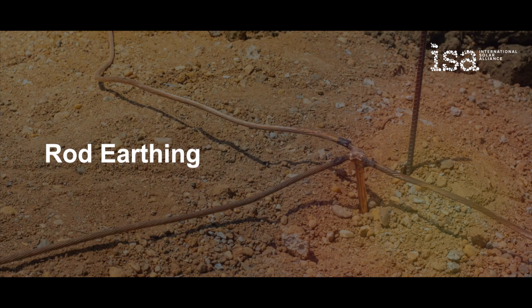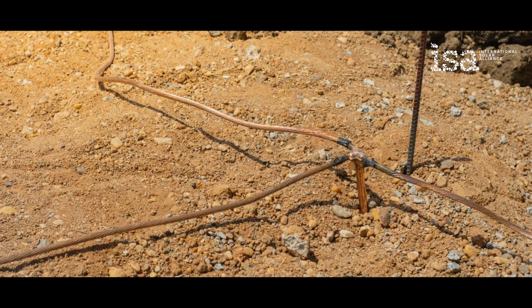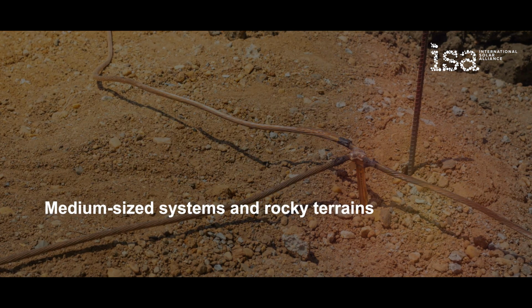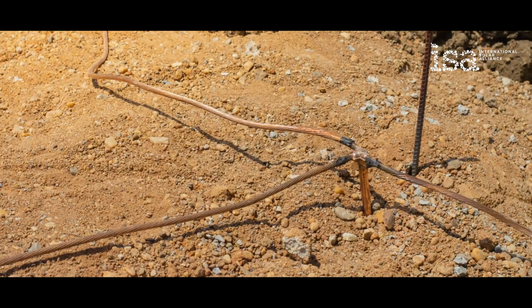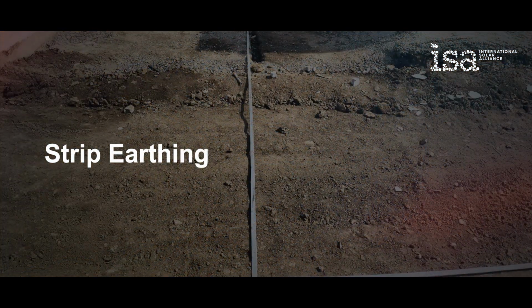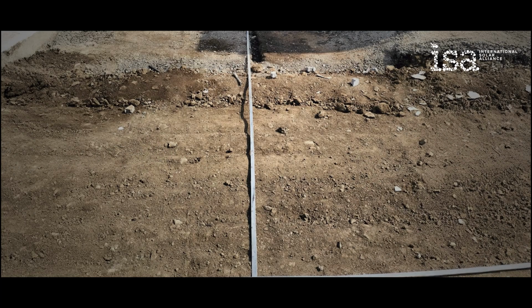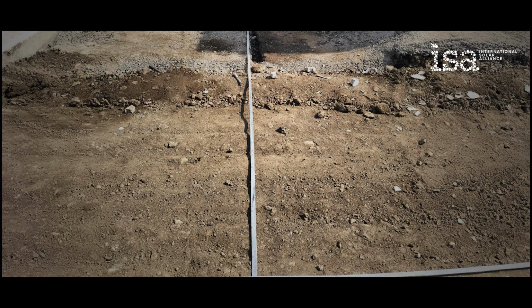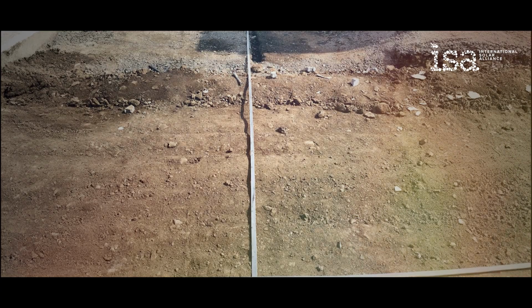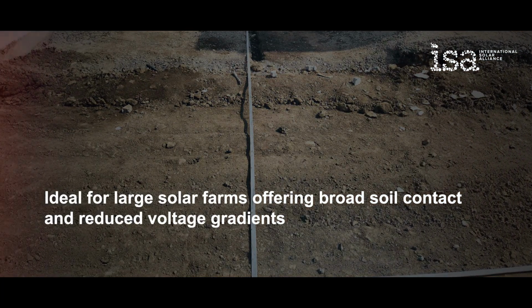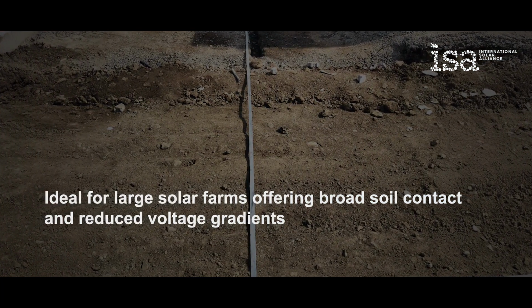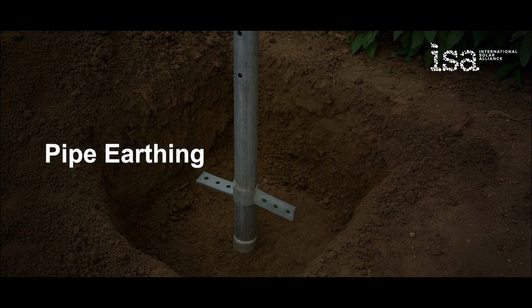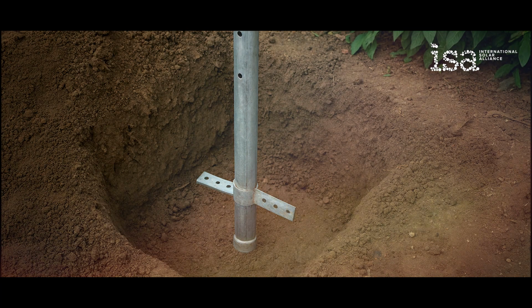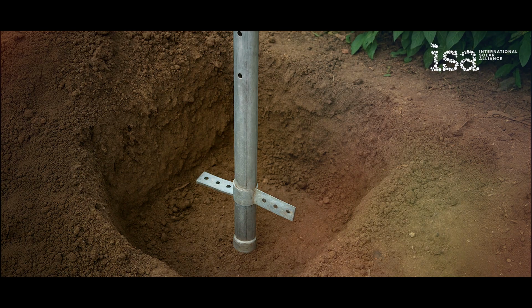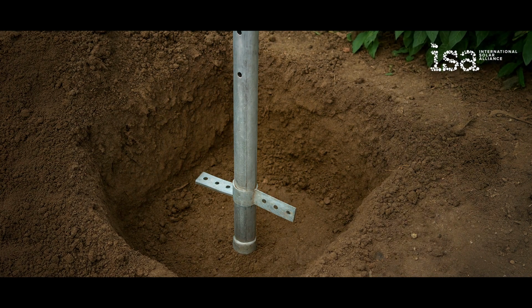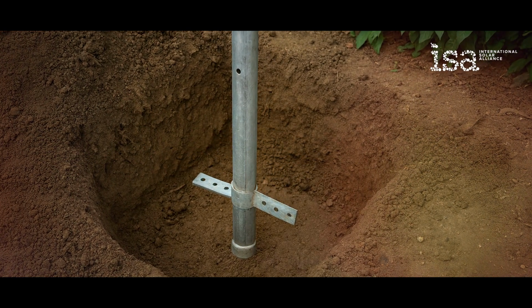Rod earthing consists of one or more metal rods driven vertically into the soil, commonly used in medium-sized systems and rocky terrains. Simple, cost-effective, and easy to expand. Strip earthing uses flat strips of copper or galvanized iron buried horizontally in a trench to provide more contact area with the soil. Ideal for large solar farms, offering broad soil contact and reduced voltage gradients. Pipe earthing employs metal pipes acting as electrodes and uses hollow galvanized pipes that retain moisture for stable resistance, commonly used for inverter and equipment grounding.